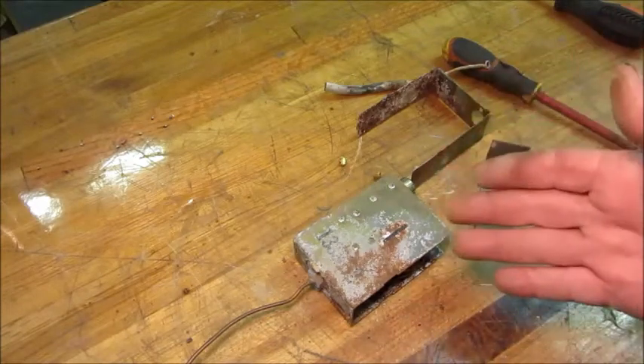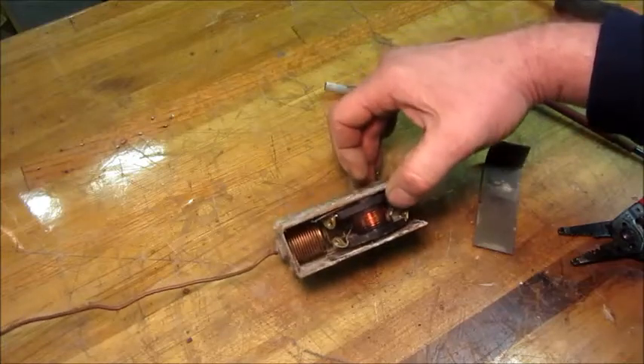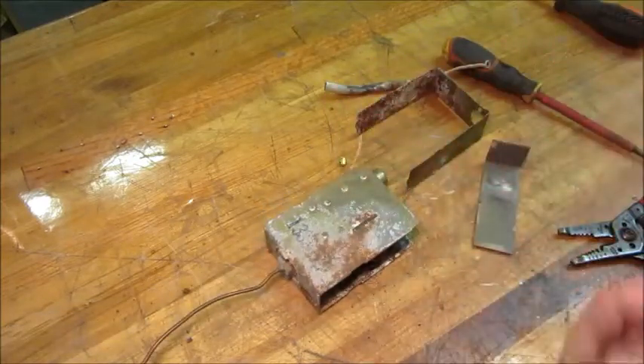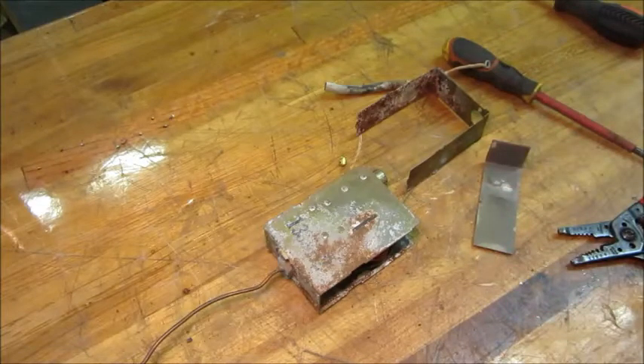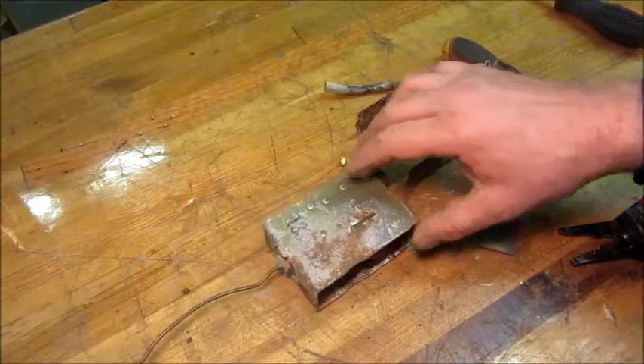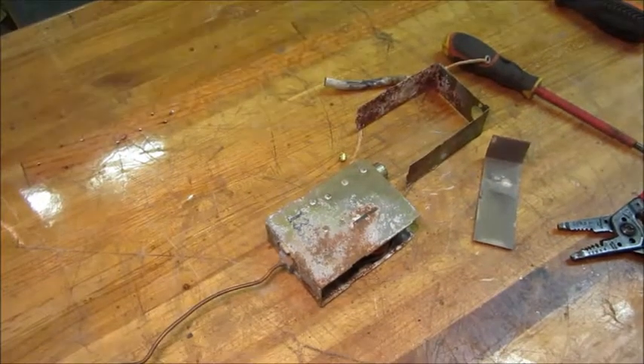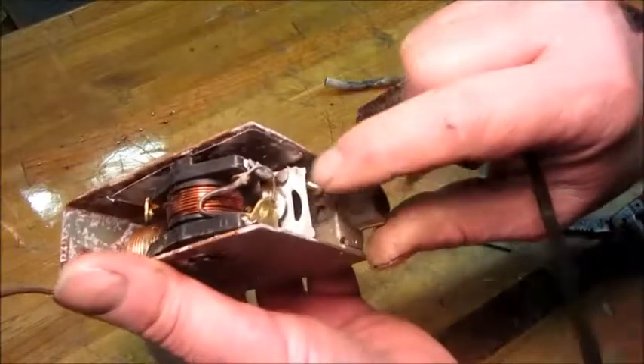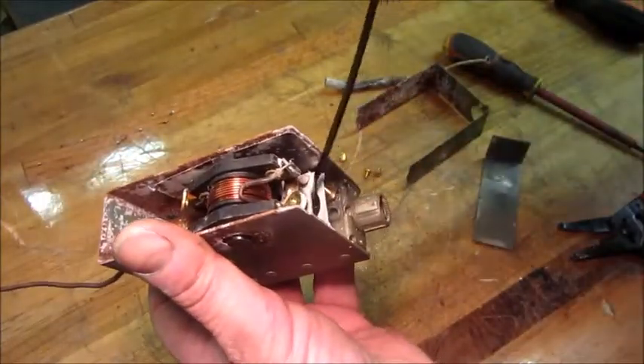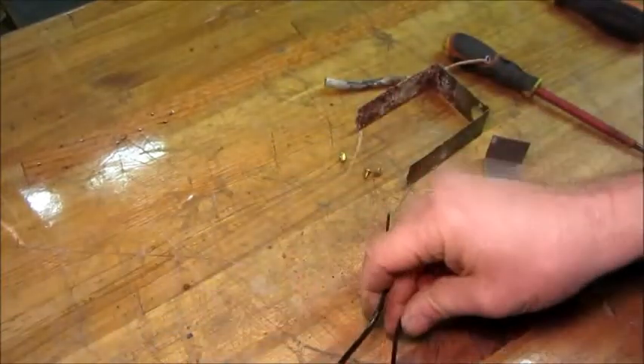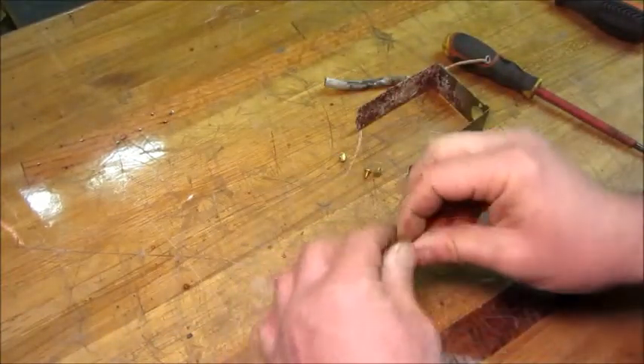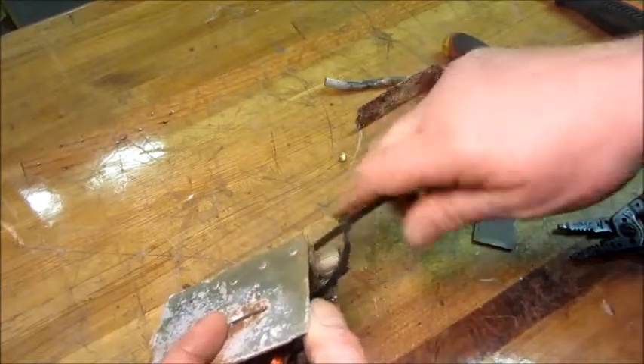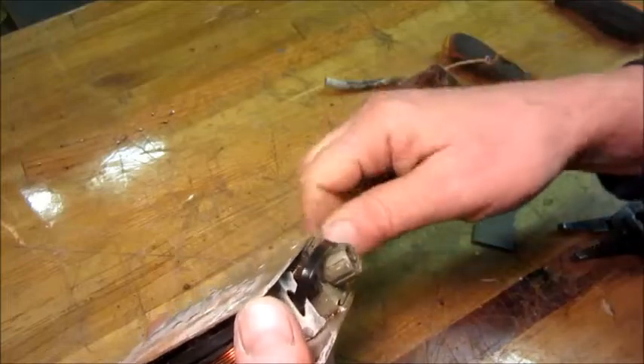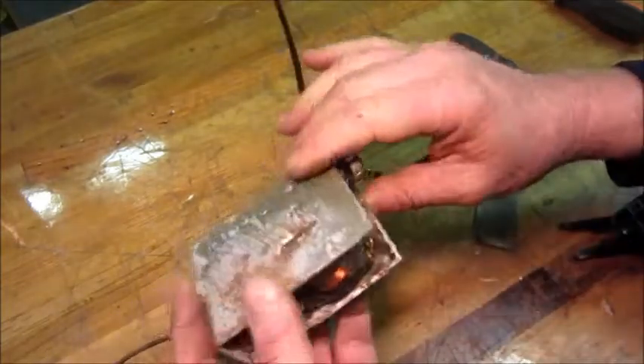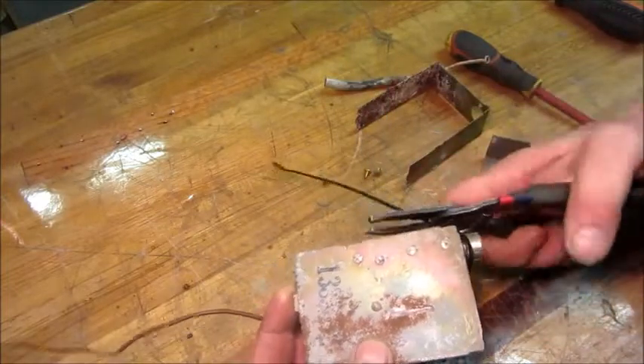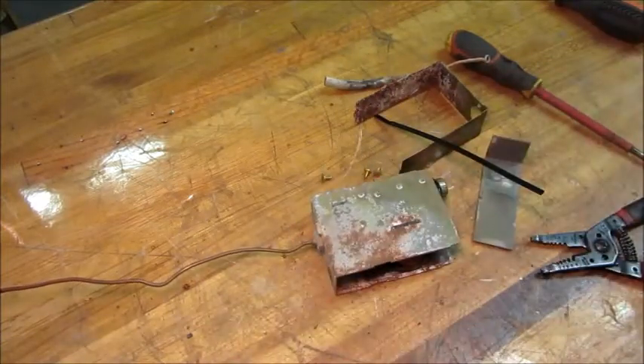So had somebody local read our forums and watched our videos and done this repair, this thing wouldn't have to go across country, but it's neither here nor there at this point, because she's here, and I think we're also going to get it painted, so all's well that ends well. And just like on the last Westinghouse, the thermostat movable arm needs to be tied back with a cable tie, because if the start relay is taken out without this tie in there, then that thermostat arm will flip all the way back, and a spring will go flying. It can be reassembled if that happens, but it's just extra work. And of course, if the spring went somewhere I can't find it, then I've got problems.